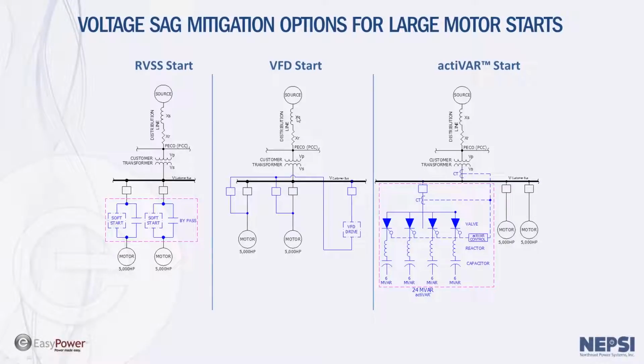Now, the VFD starter is kind of a gold standard here. It always works. You can always produce full torque from the motor. It reduces both voltage and frequency to the motor, and therefore it is able to achieve full torque while basically maintaining terminal voltage, or nominal voltage, at the motor.